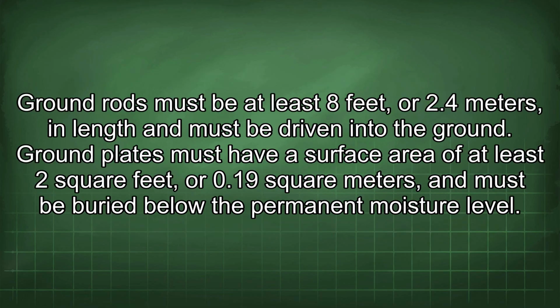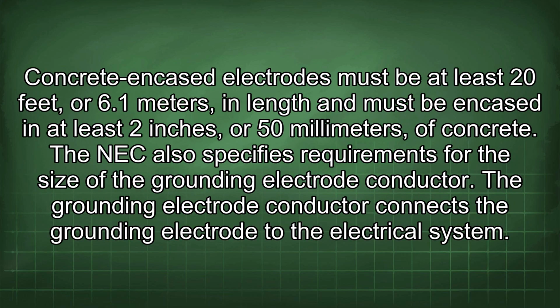Ground rods must be at least 8 feet, or 2.4 meters, in length and must be driven into the ground. Ground plates must have a surface area of at least 2 square feet, or 0.19 square meters, and must be buried below the permanent moisture level. Concrete encased electrodes must be at least 20 feet, or 6.1 meters, in length and must be encased in at least 2 inches, or 50 millimeters, of concrete.